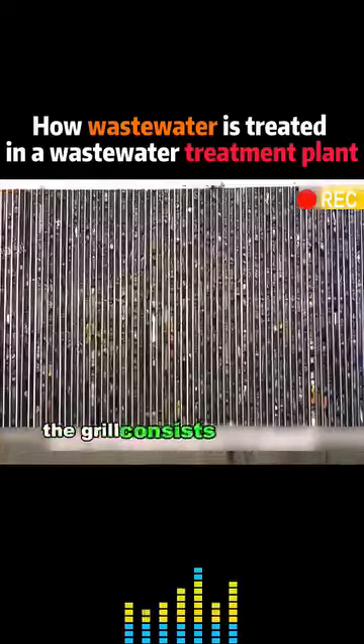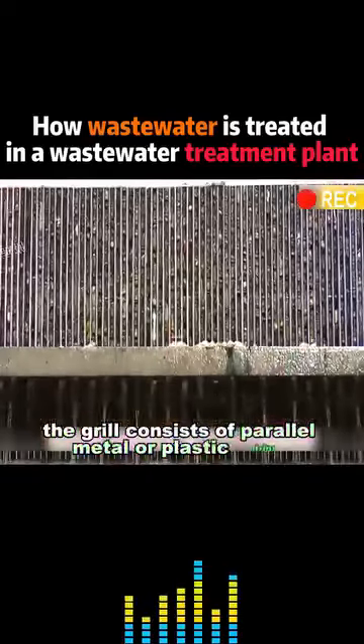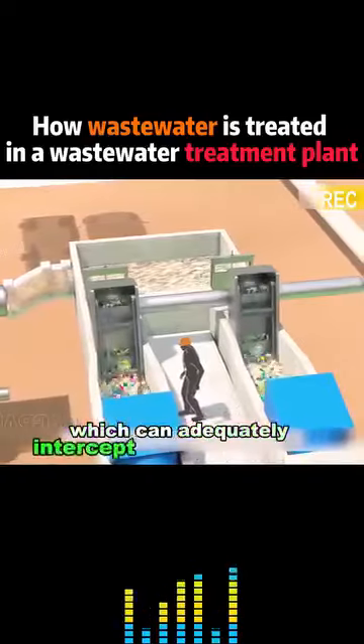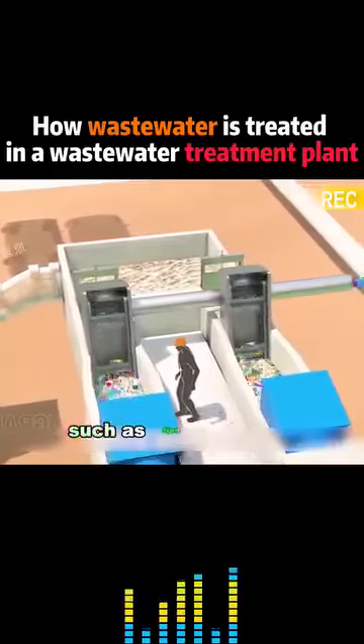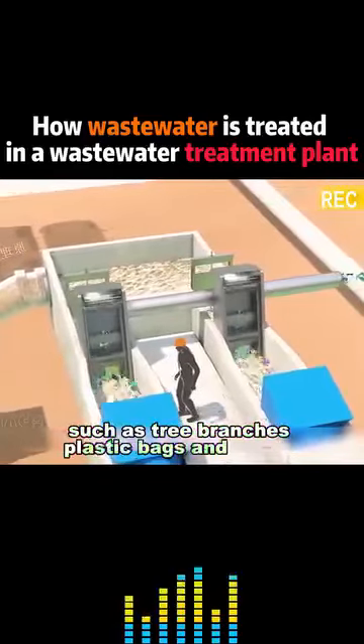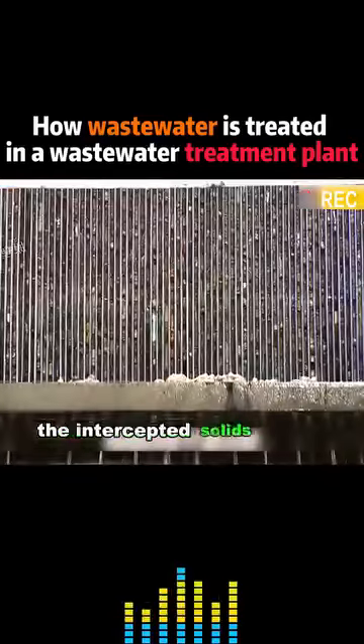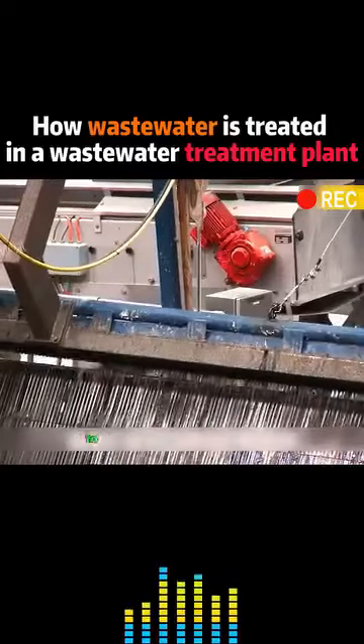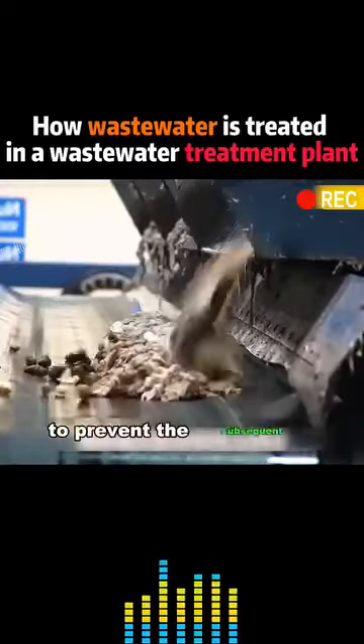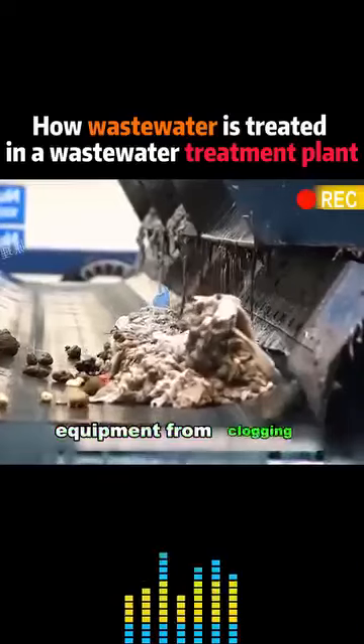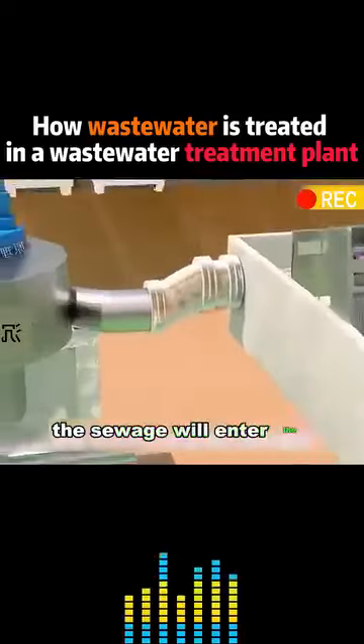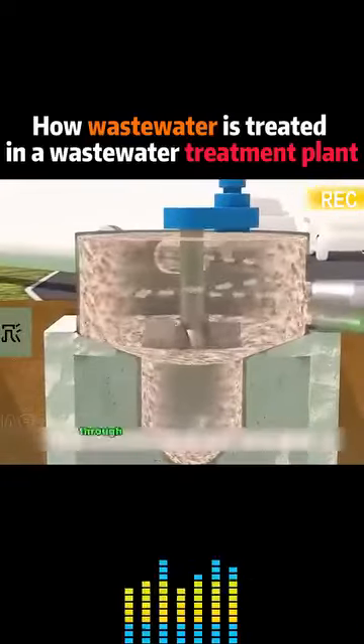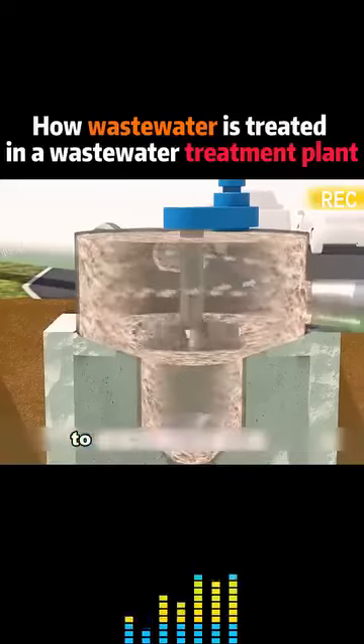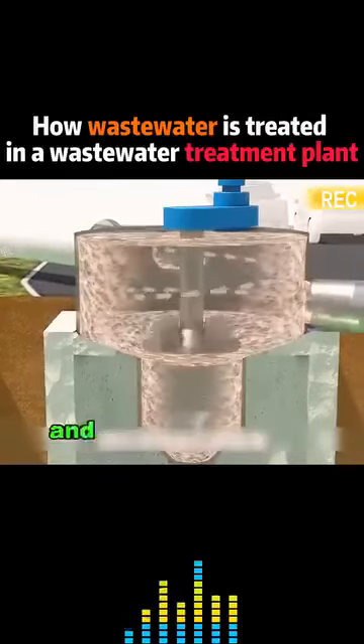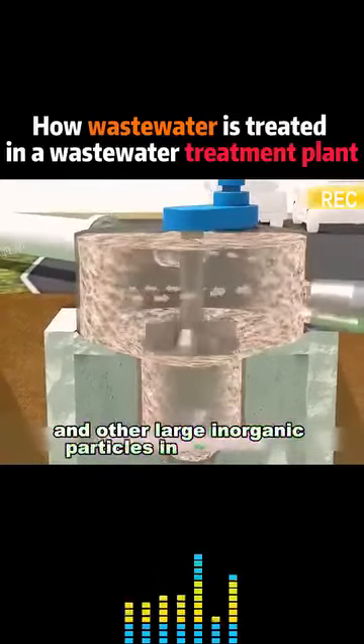The grill consists of parallel metal or plastic strips, which can adequately intercept larger solid wastes, such as tree branches, plastic bags, and stones. The intercepted solids will be scraped by the scraper to a special channel to prevent the subsequent treatment equipment from clogging. Then the sewage will enter the sand sedimentation tank, where, through the principle of gravity, settling removes sand, cinder, and other large inorganic particles in the sewage.